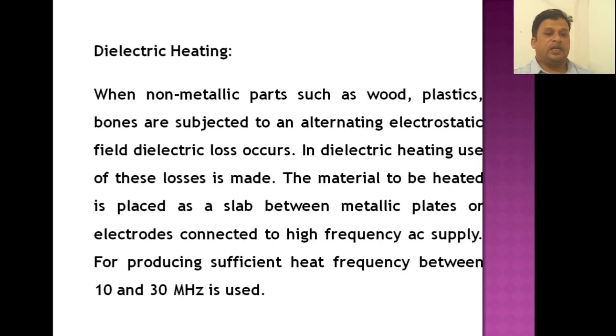In dielectric heating, use of these losses is made. Whatever dielectric loss occurs when non-metallic parts such as wood and plastic are subjected to an alternating electrostatic field is used in dielectric heating. The material to be heated is placed as a slab between metallic plates or electrodes connected to a high frequency supply.